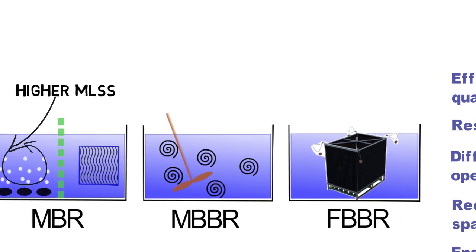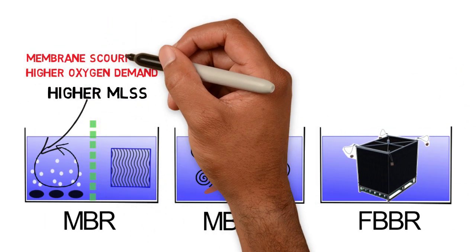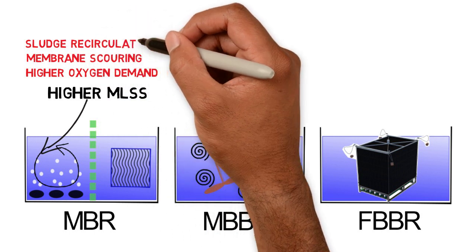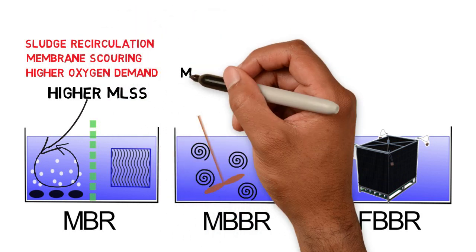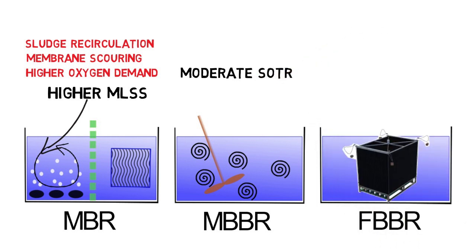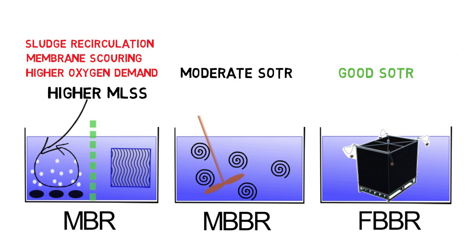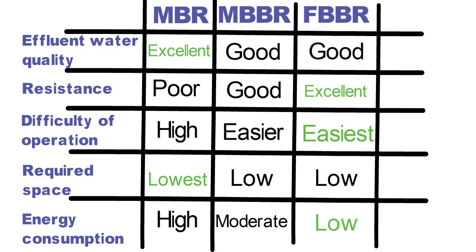Energy consumption. Due to higher MLSS permanent back washing of the membrane and fouling prevention, MBRs need a high air volume thus have a high energy demand and cost. FBBRs require less energy than MBBRs because the air supply of the biofilm is installed directly underneath the fill media, which results in a better oxygen intake.